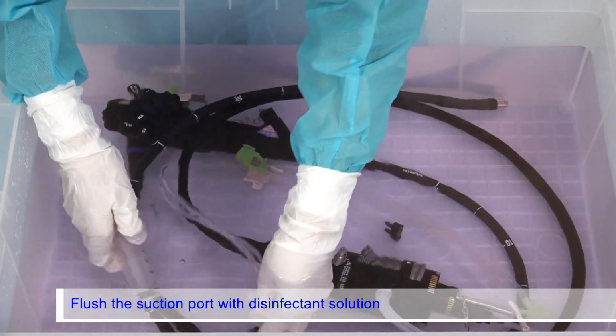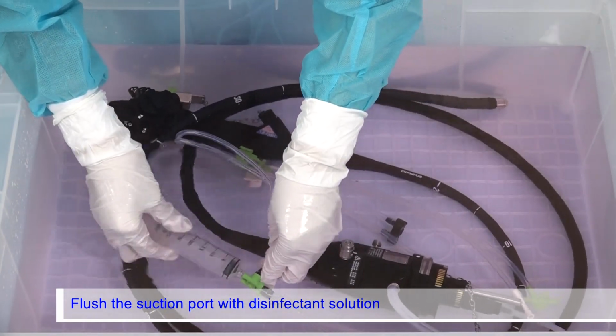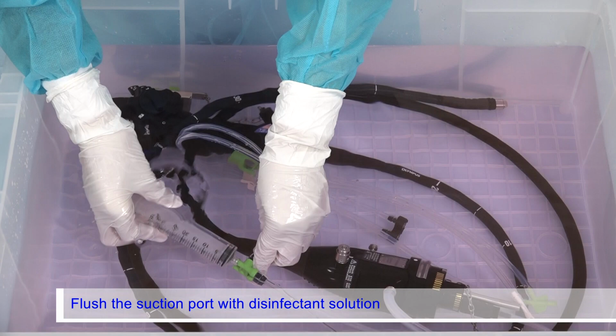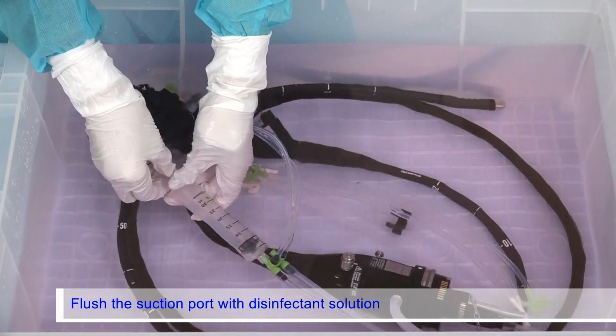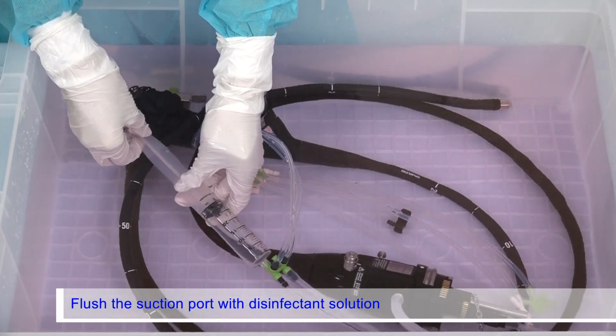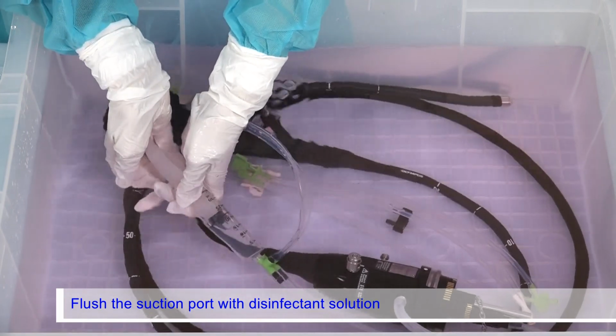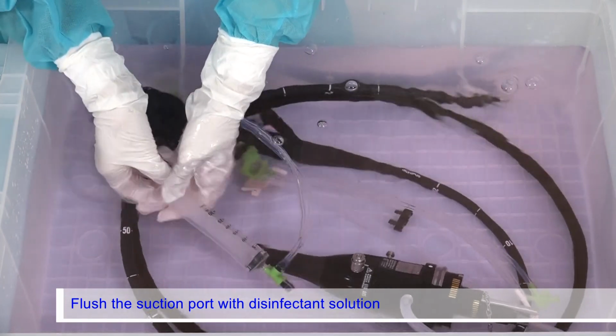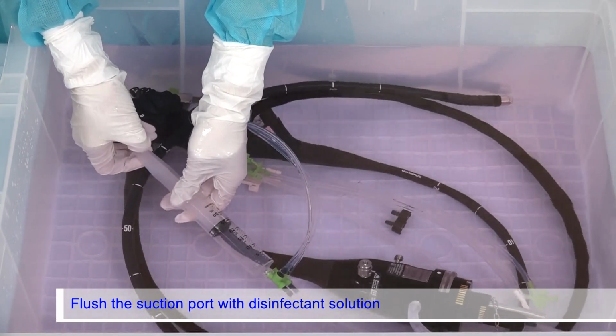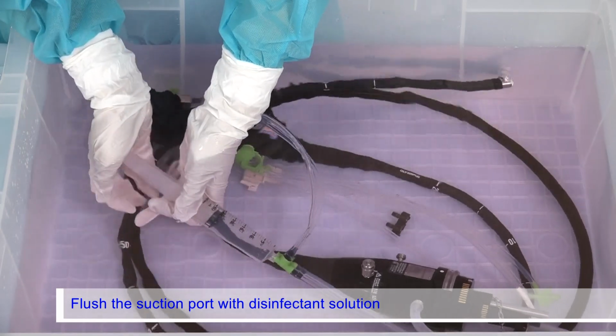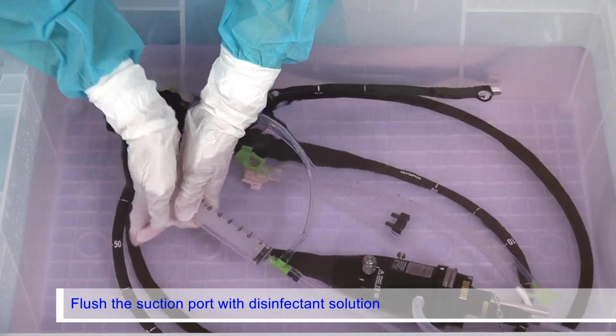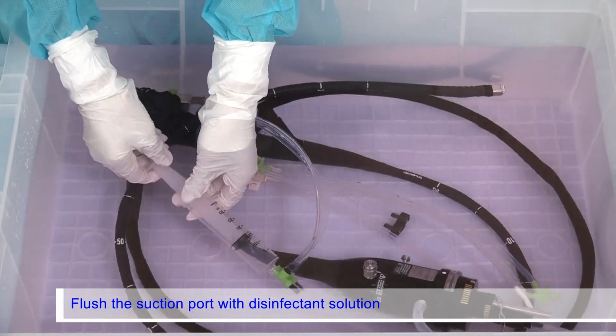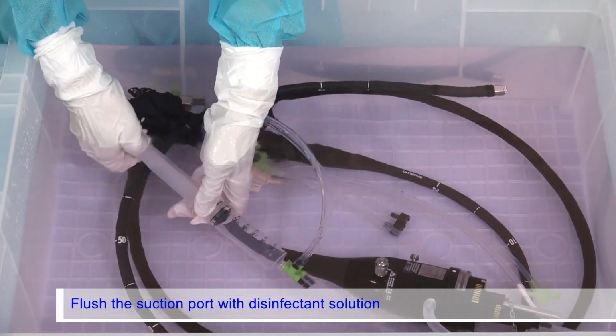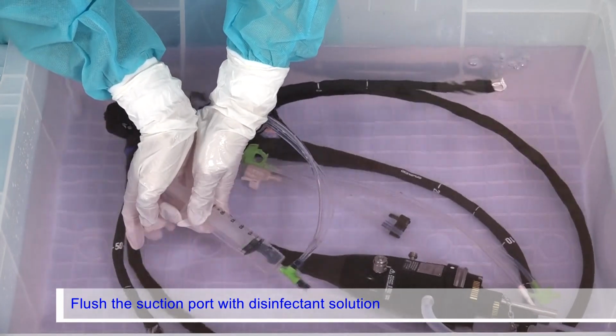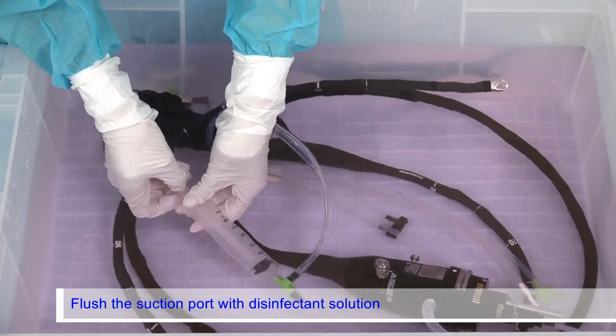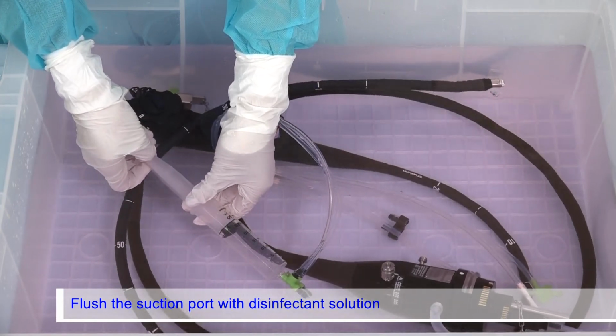Confirm that the suction port of the injection tube is completely immersed in the disinfectant solution. Attach the 30 milliliter syringe to the suction channel port of the injection tube. While immersing the syringe completely in the disinfectant solution, slowly pull the syringe plunger to fill the syringe with the disinfectant solution. Then, forcefully push in the plunger to flush the suction channel with 30 milliliters of the disinfectant solution. Repeat the step 5 more times.